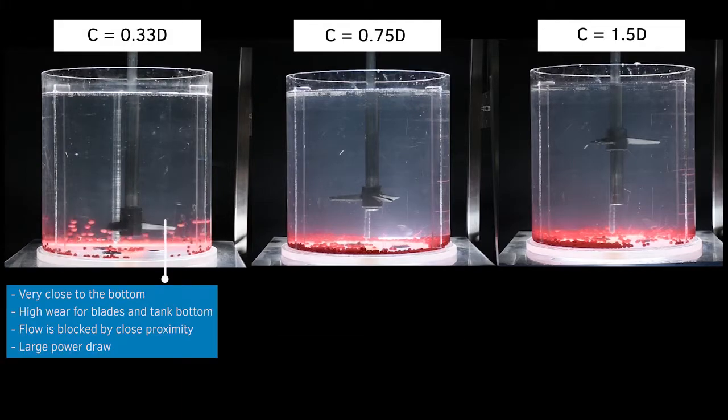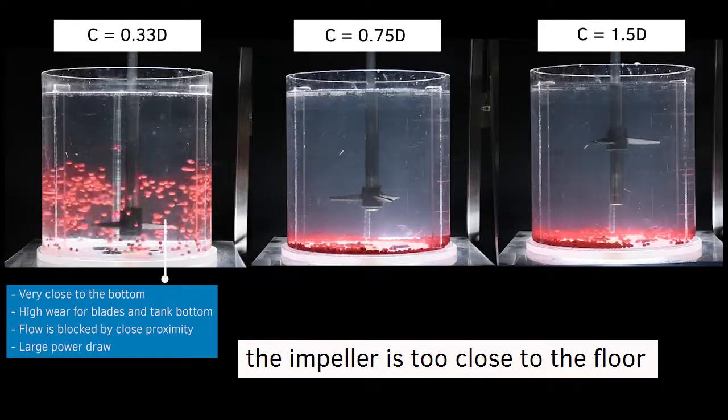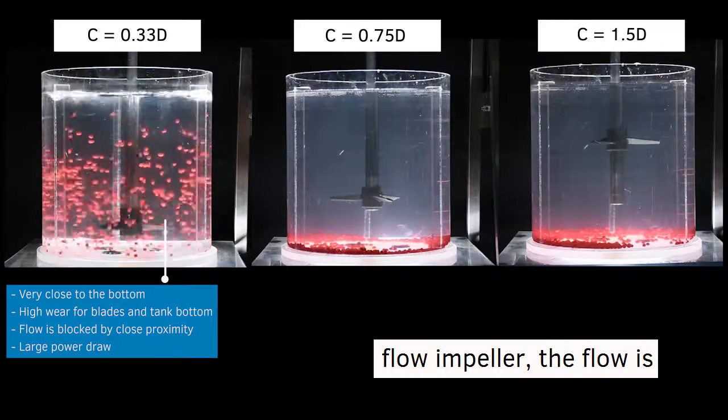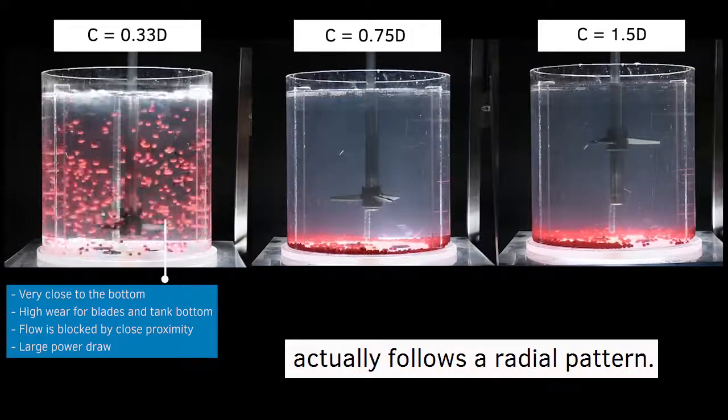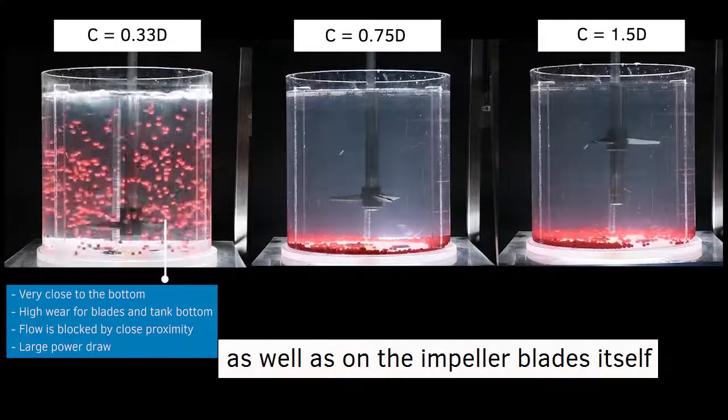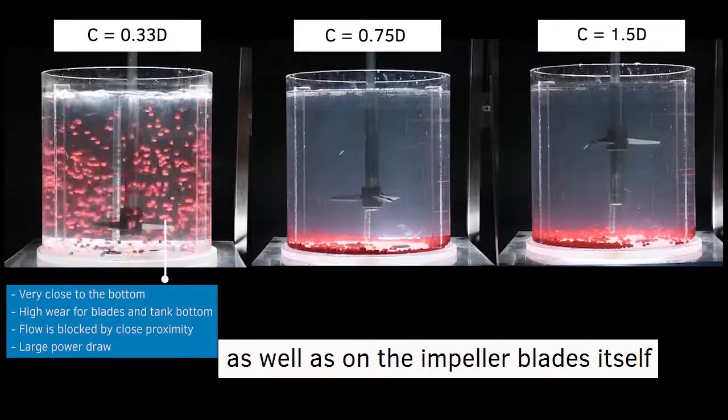In the first tank, the impeller is too close to the floor. Although it is an axial flow impeller, the flow actually follows a radial pattern. You will experience high wear on the floor of the tank as well as on the impeller blade itself.